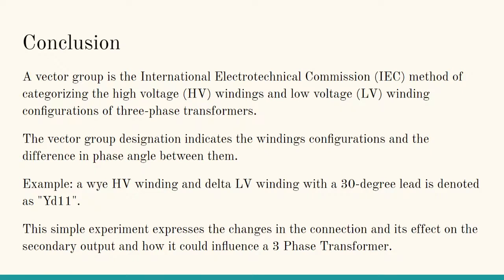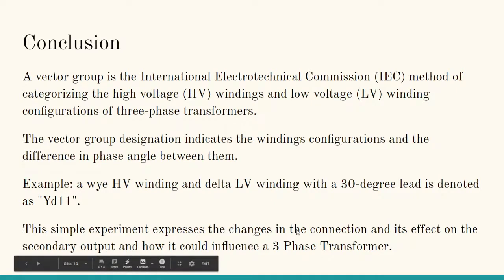Vector groups are the IEC (International Electrotechnical Commission) system for categorizing high-voltage and low-voltage windings and their configurations in three-phase transformers. What changes is the phase angle — there is a phase delay between primary voltage and currents that results in a lead or lag — and the secondary polarity of the winding. For example, a Y connection for the HV side and a delta connection on the LV side with a 30-degree lead is denoted by Yd11, shown in the phasor diagram.